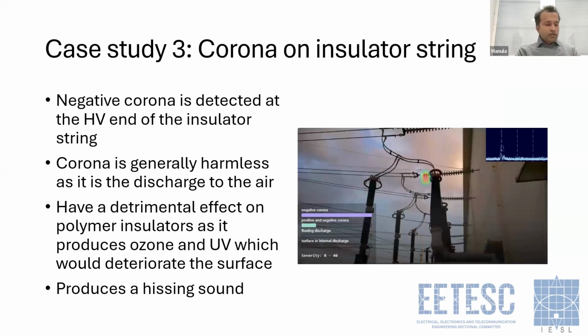Okay, in our third example, here we have a similar air insulated outdoor substation, and here again we are detecting some kind of partial discharge in this insulator string high voltage end, but this time the PRPD pattern suggests it as a corona discharge, particularly negative corona. You can see in the PRPD pattern we have only one peak. We don't have another peak in the second half cycle. So mostly this PRPD pattern suggests the type of partial discharge as corona discharge. And as we know, corona discharge is the discharge into air, so usually it is a harmless phenomenon. It wouldn't cause that much trouble in this kind of installation.